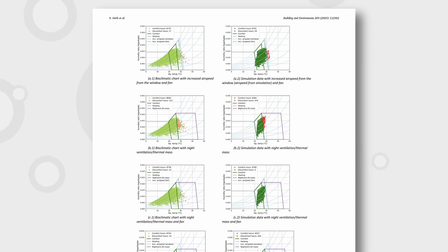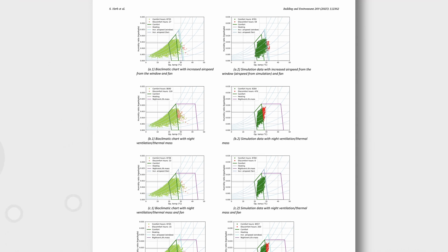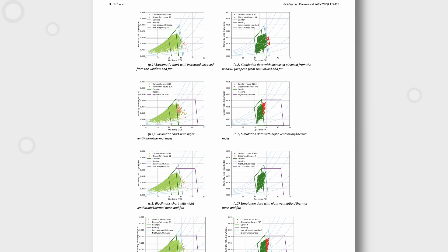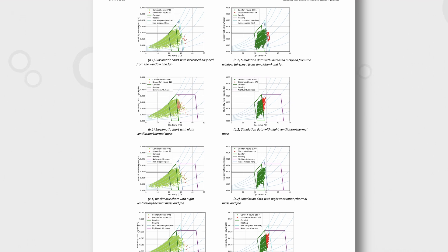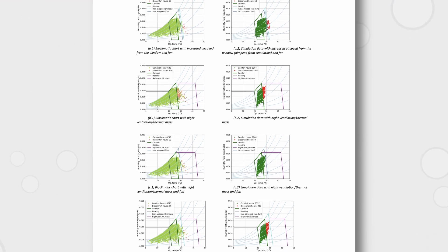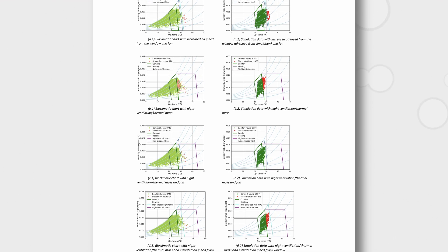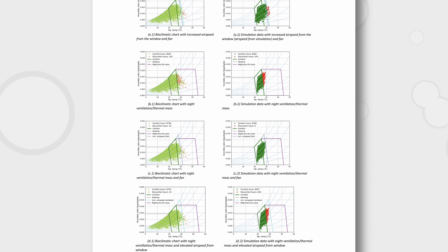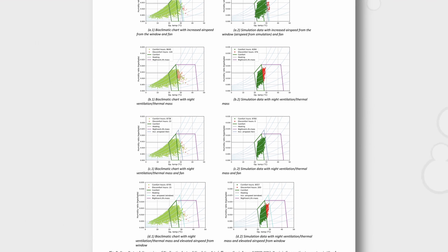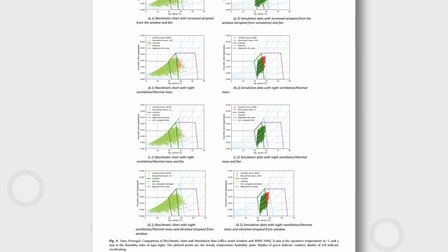For example, when combining night ventilation, thermal mass, and elevated air speed from an open window, the bioclimatic chart significantly under-predicts overheating hours because it cannot physically assume that elevated air speed from a window can be combined with thermal mass. In fact, in up to 21% of the cases, the bioclimatic chart incorrectly predicts whether a building needs an AC system, sometimes missing the need for AC altogether.